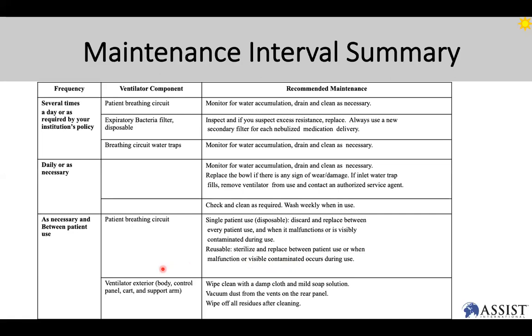If it is in a maintenance area, so not in the patient care area, you bring the ventilator to a maintenance area, you have to vacuum dust off the ventilators on the rear panel, ensuring that you wipe off all residues after cleaning. If you want the recommendation of cleaning solutions, we covered that last week. You can reference the materials from last week, or we're happy to get that information out to you if you ask for it.